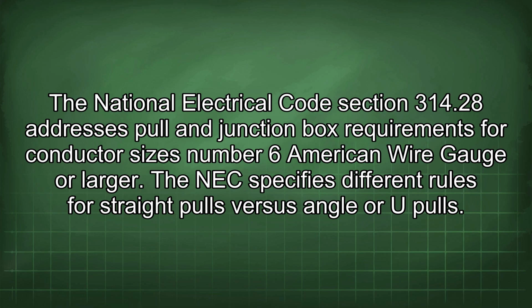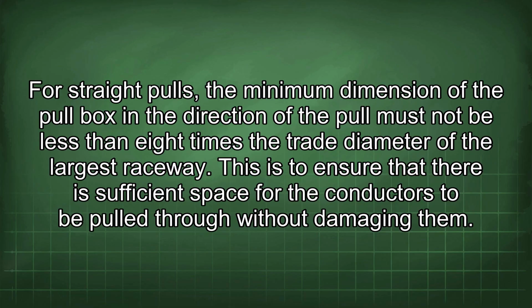314.28 addresses pull and junction box requirements for conductor sizes number 6 American wire gauge or larger. The NEC specifies different rules for straight pulls versus angle or U-pulls. For straight pulls, the minimum dimension of the pull box in the direction of the pull must not be less than 8 times the trade diameter of the largest raceway. This is to ensure that there is sufficient space for the conductors to be pulled through without damaging them.